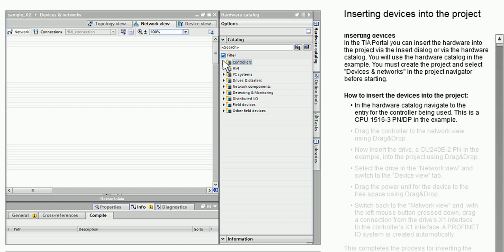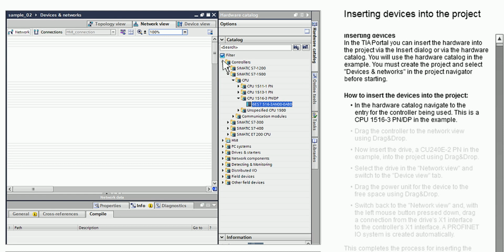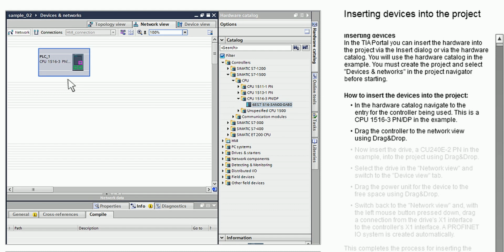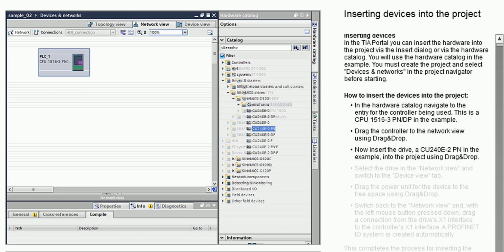In the Hardware catalog, navigate to the entry for the controller being used. This is a CPU 1516-3 PN/DP in the example. Drag the controller to the network view using drag and drop. Now insert the drive, a CU240E-2 PN in the example, into the project using drag and drop.